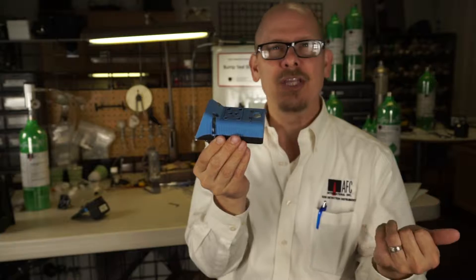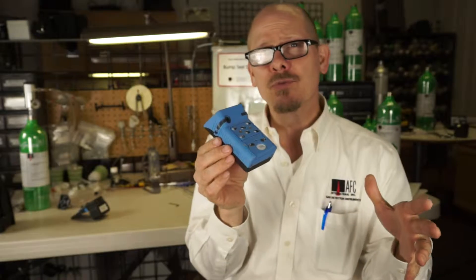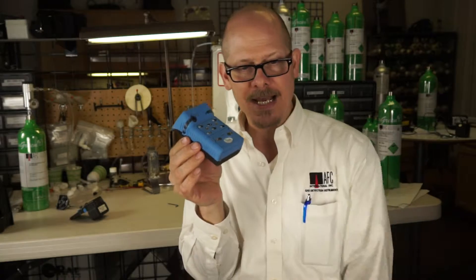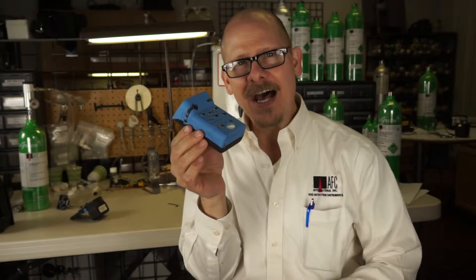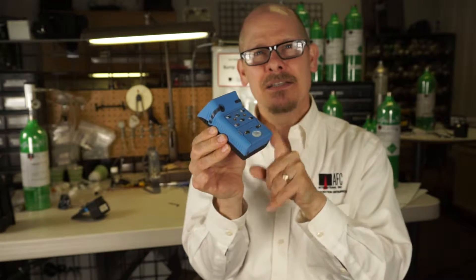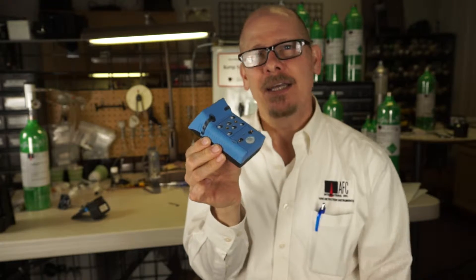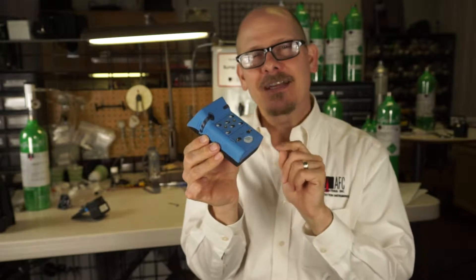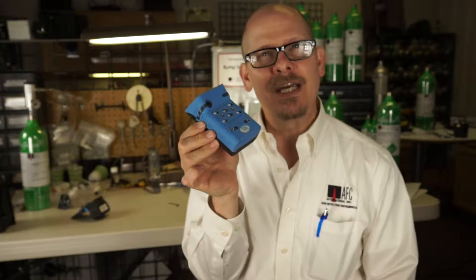Those gas sensors range from H2S, CO, LEL, and O2 — the basic four gases for confined space — all the way through toxic exotics like ammonia, chlorine, chlorine dioxide, ethylene oxide, HF, phosphine, phosgene, a 10.6 PID sensor, infrared for CO2, and an infrared sensor for combustible 0 to 100% LEL. In fact, the LEL and CO2 infrared sensors can be done on one physical sensor, so we can actually detect two gases there.